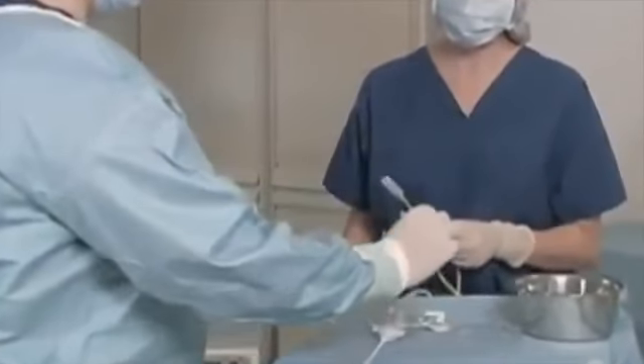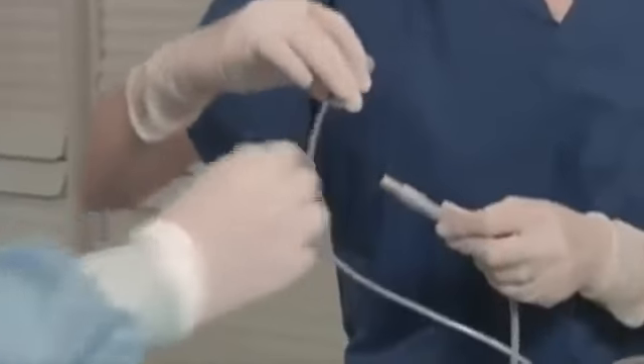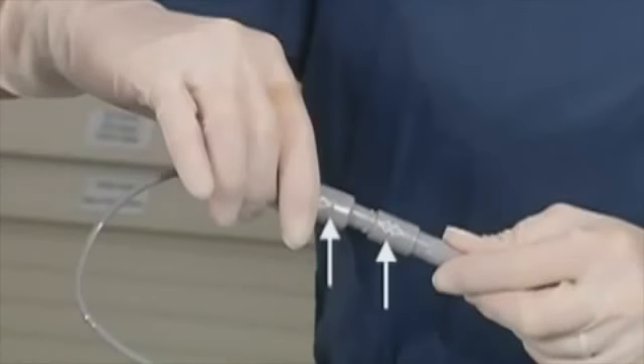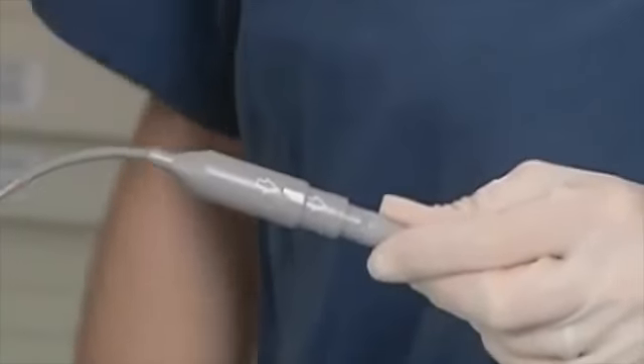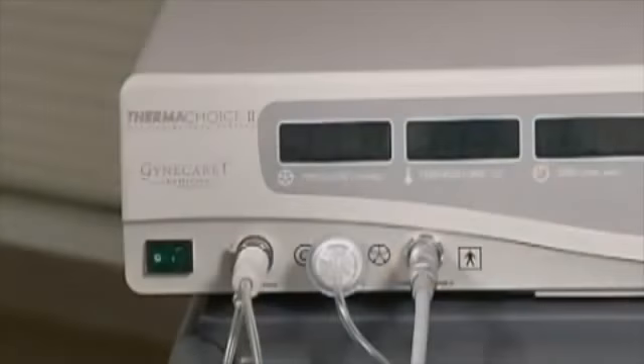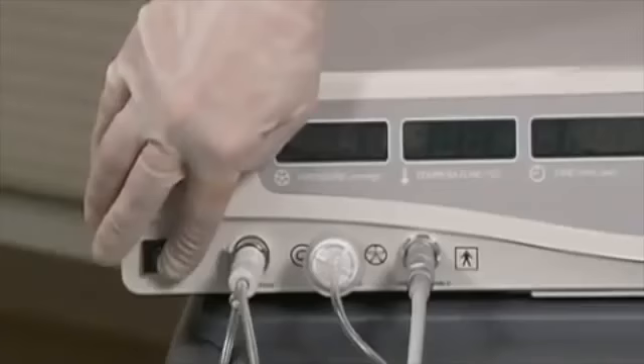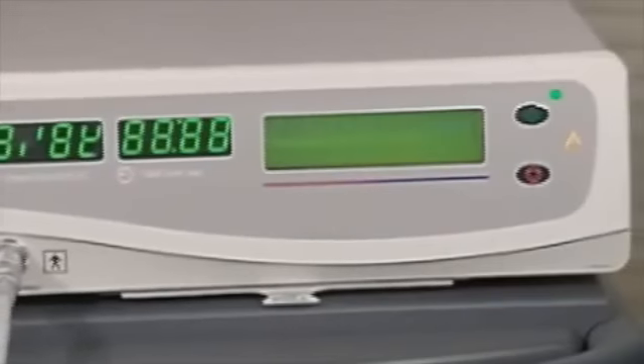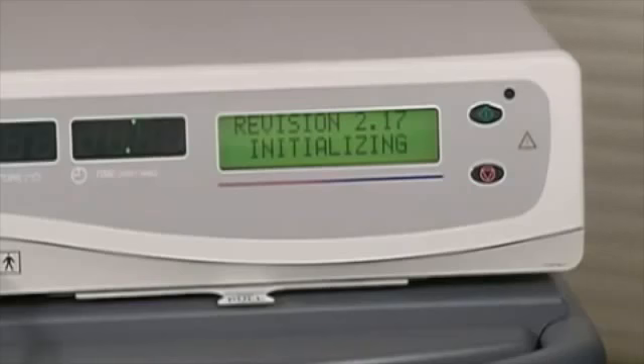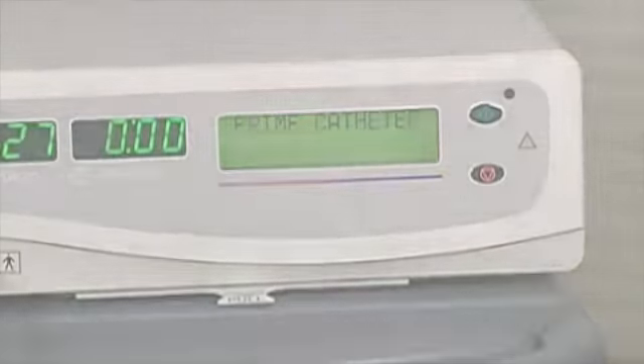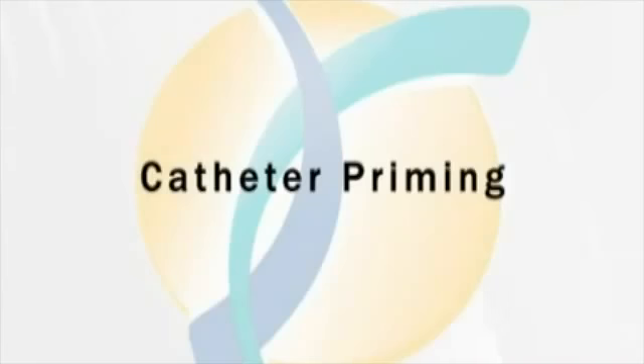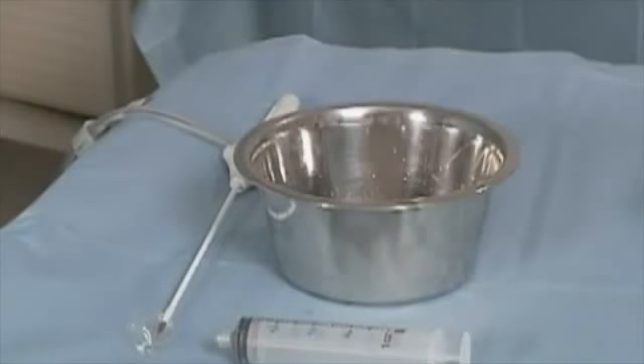The other end of the umbilical cable is then connected with the catheter's extended cable receptacle. The arrows of the cable should line up with the white notch on the catheter's cable receptacle. As they are secured together, you will hear and feel a click. You are now ready to turn the controller power switch on. With the power on and the catheter fully connected, the message display will read Prime Catheter. The catheter is then primed.